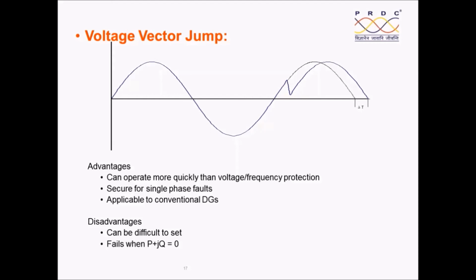Therefore, we need to do system studies to find out that whenever a fault occurs in the system, the vector shift relay should not operate. But whenever the grid line is open or the grid side farther end breaker gets open, at that time there is a vector shift using which we can ensure proper islanding. But this fails when the initial power flow from the captive power plant to the grid line is 0. Then you may not see the vector shift. Therefore, the vector shift relay may not operate. Then we need to look into various other functions and ensure that proper islanding is there.